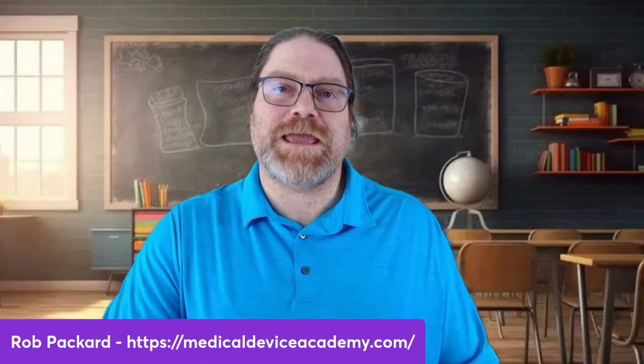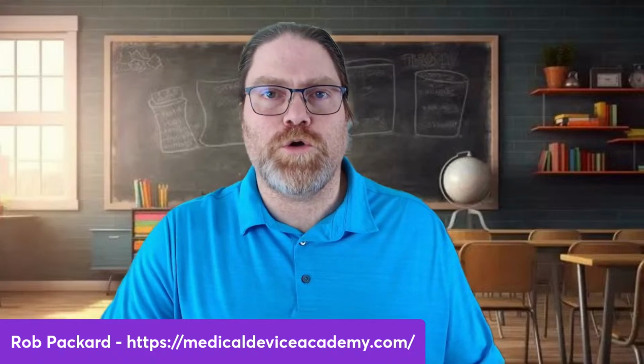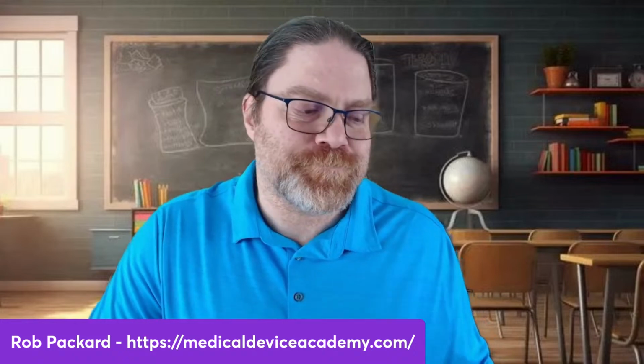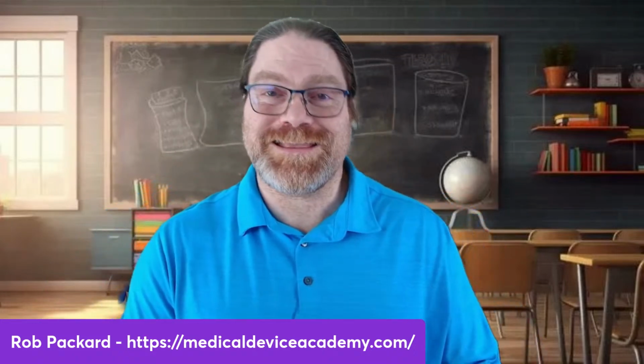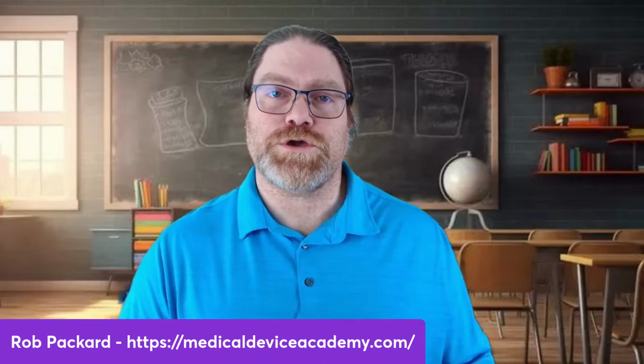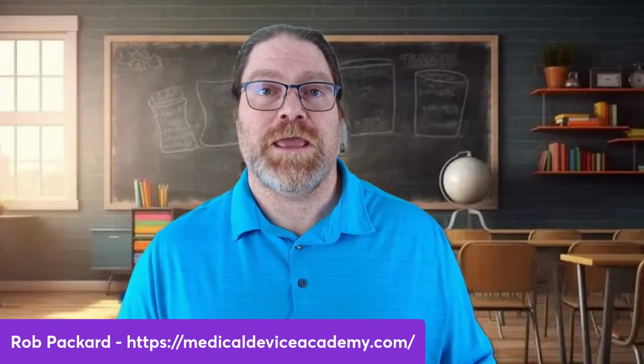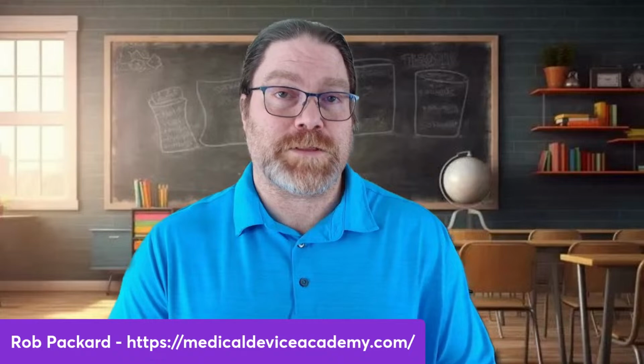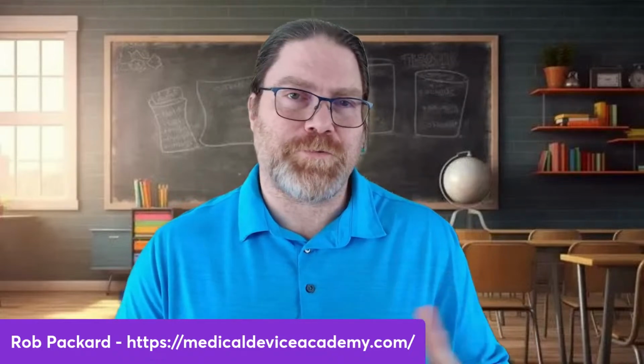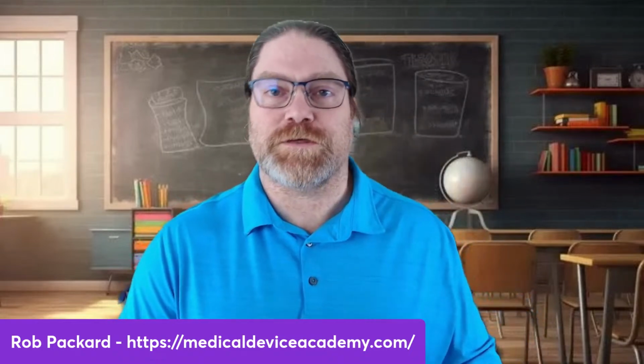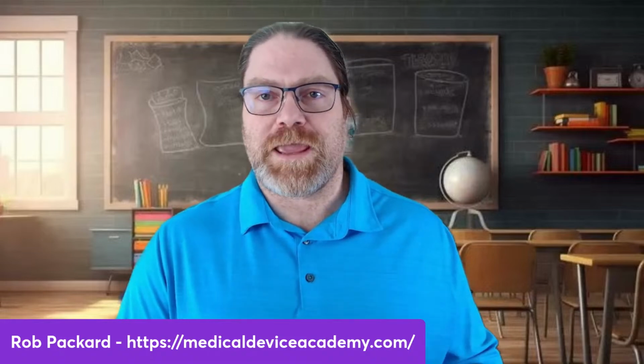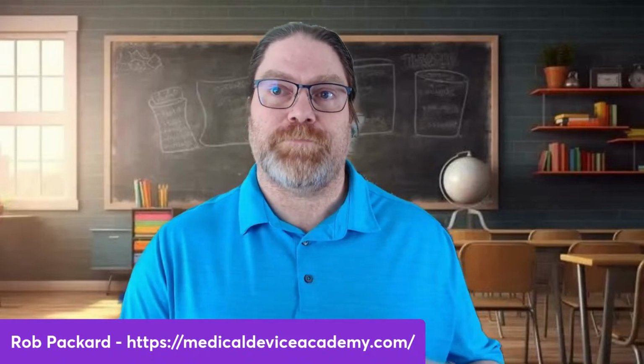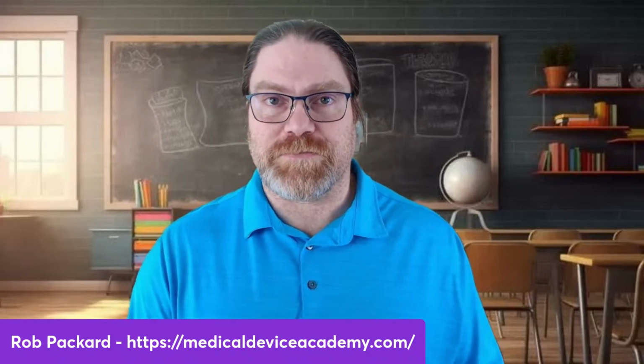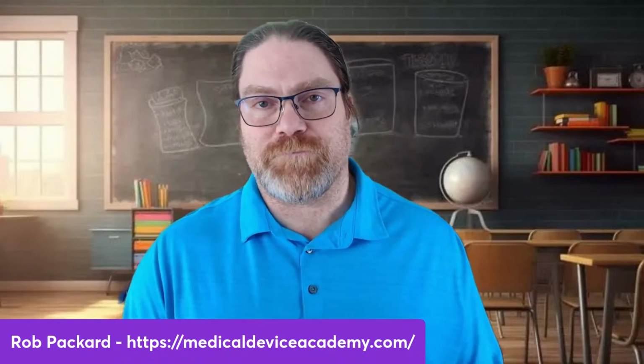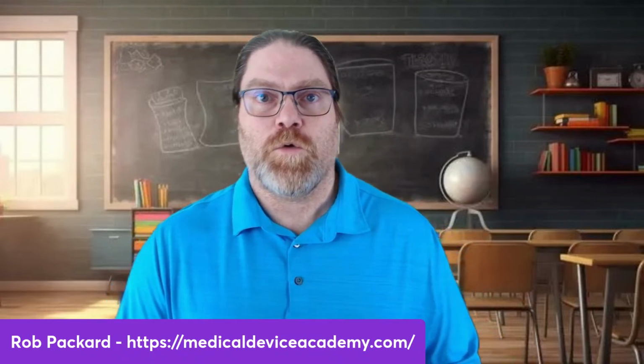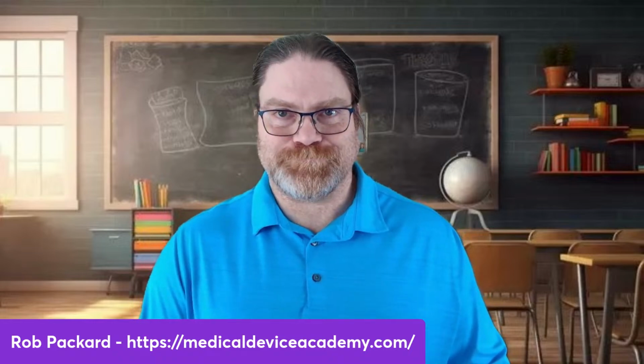Do you have any idea what IQ, OQ, and PQ stand for? IQ is installation qualification, OQ is operational qualification, and PQ is performance qualification. I've heard a couple other variations of those three acronyms and what they mean, but those are the three acronyms that we use to describe the three traditional parts of process validation used by the medical device industry and the pharmaceutical industry when you have automated equipment.